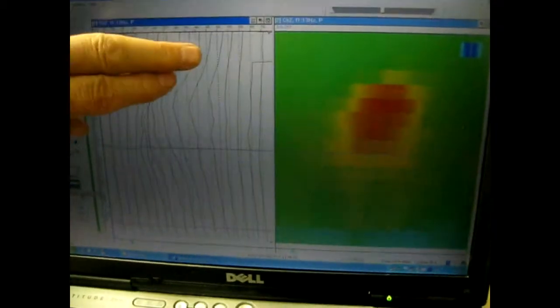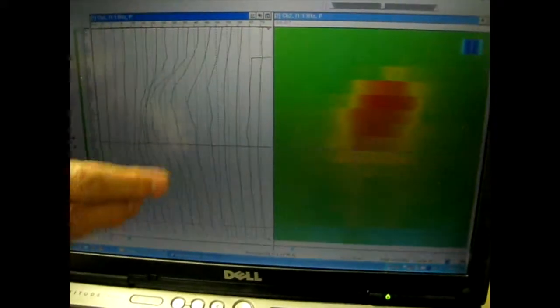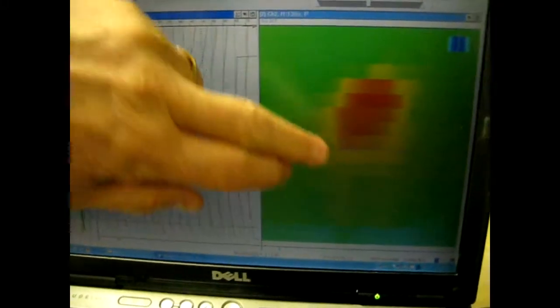So less than a minute later you have your image of the corrosion appearing on the screen. Here are the deviations in the strip chart showing the magnetic field deviations, and here's the image of the corrosion, with darker colors meaning a deeper corrosion spot.